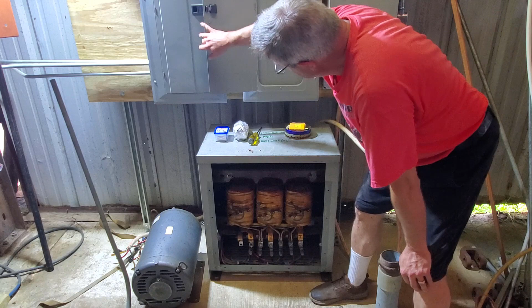This is going to be more or less its permanent home underneath the panels, right next to this guy, which I haven't talked about yet. This is a 45 kVA, 208Y 120 to 460 transformer, and it's surplus. Normally you hook up the high voltage to the transformer, and it generates single phase or low voltage 3-phase power for an installation. Like if you have 220 volt equipment, or 110 volt for lighting, this will give you that, because most motors will run on 208 volts.